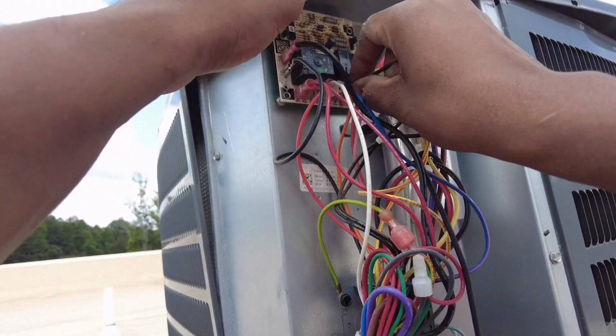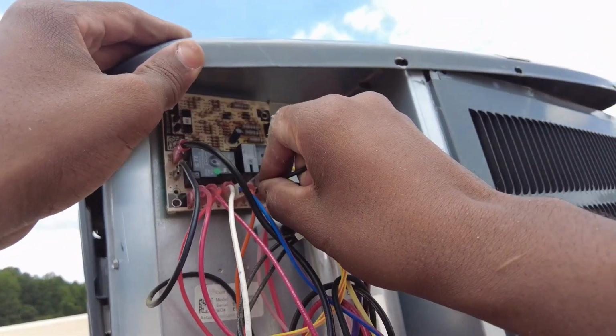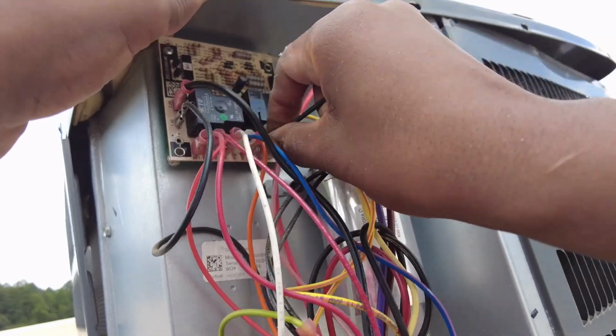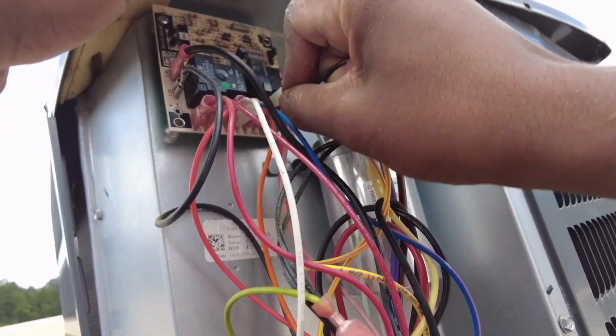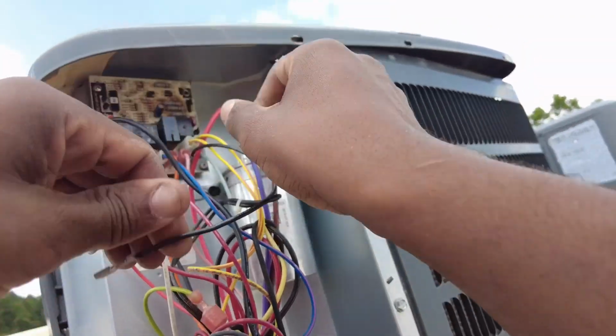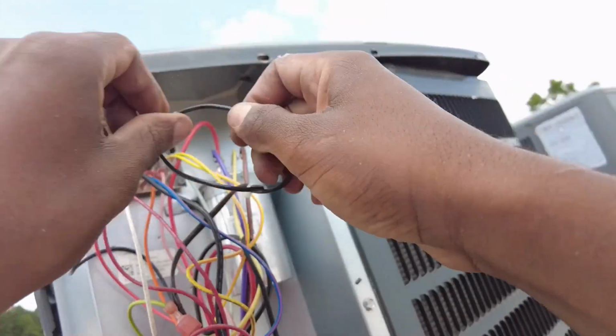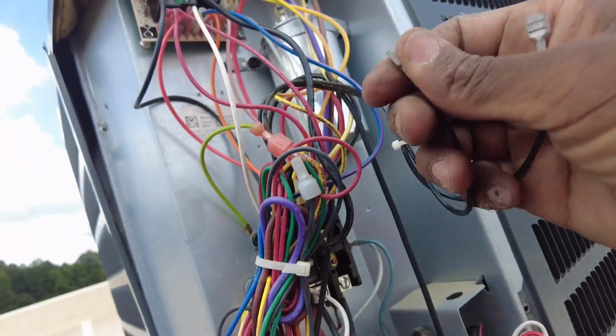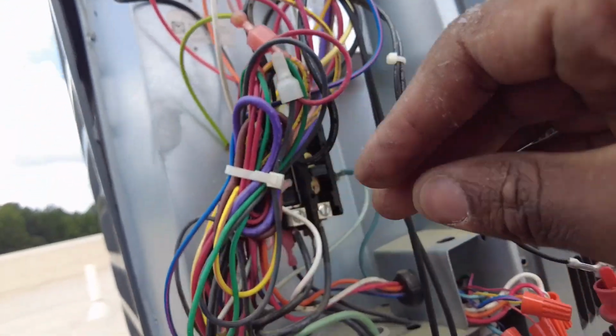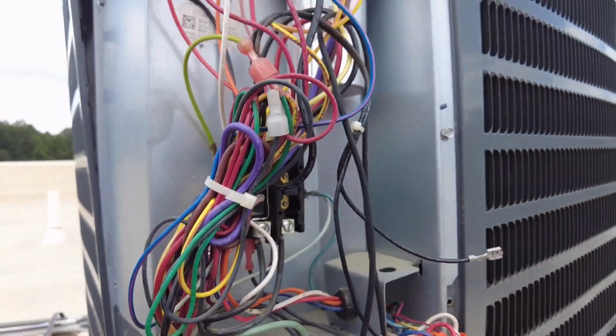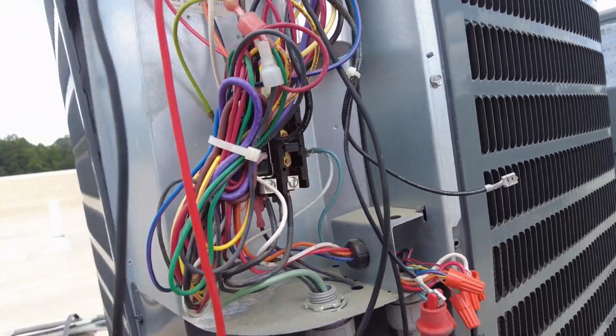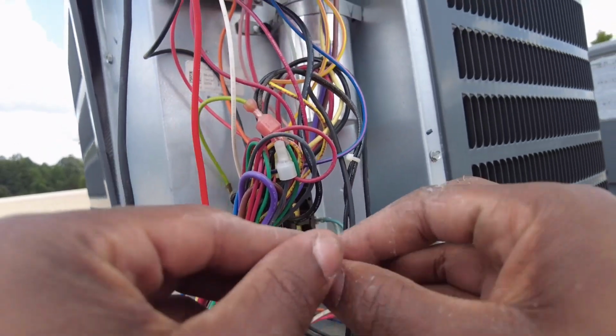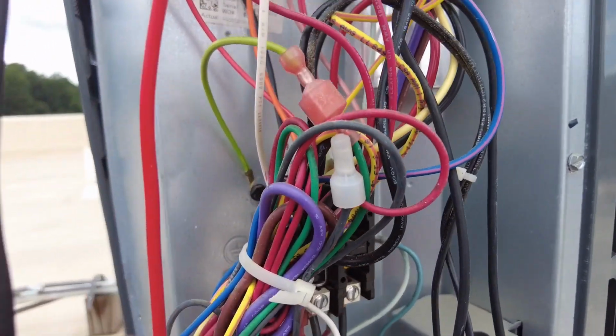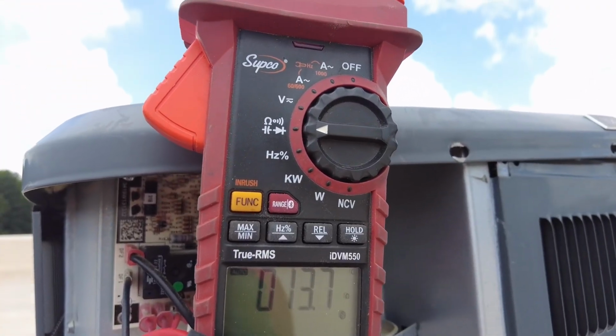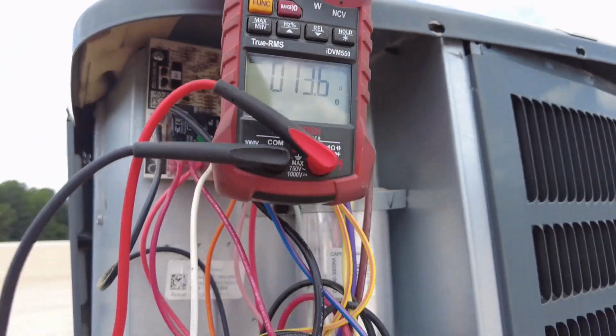Just gonna check the reversing valve real quick. So we got, these spade terminals are insanely tight, much tighter than normal. Got one on one side there. I'm just gonna go ahead and do like such. 13 ohms, that looks good to me.